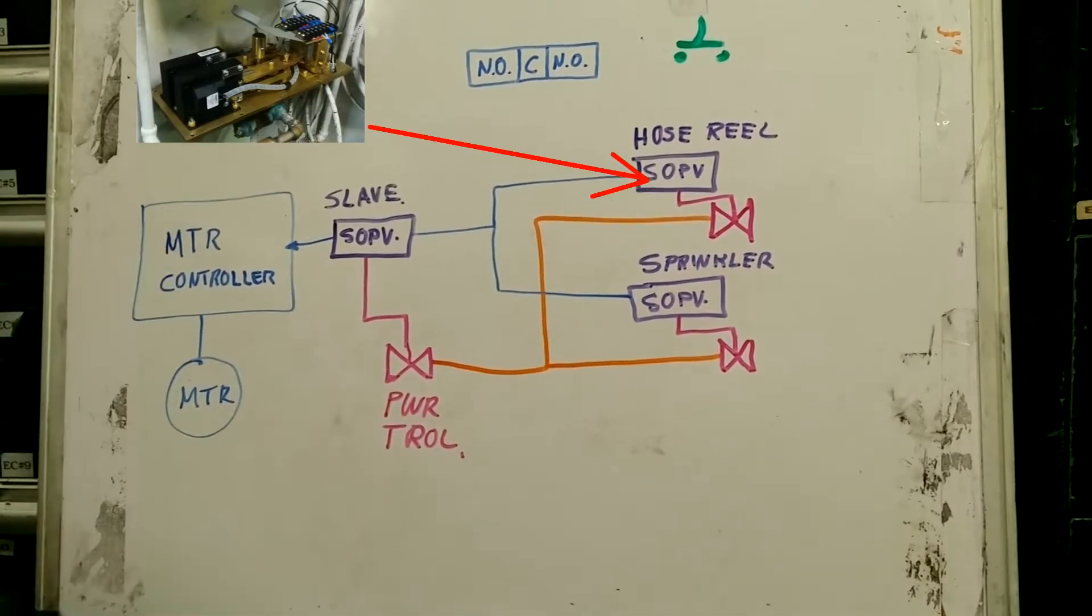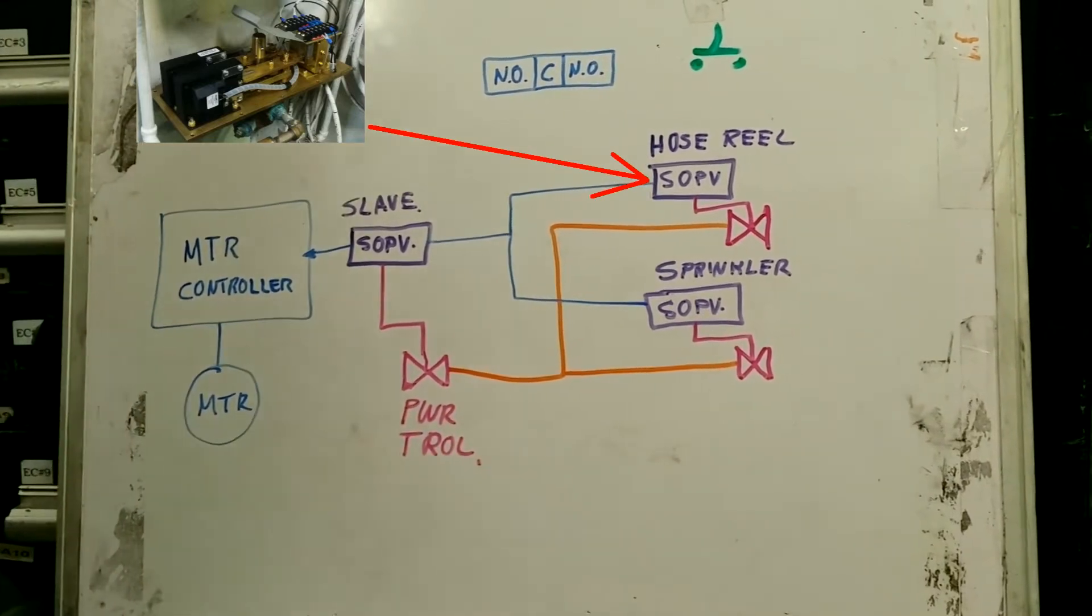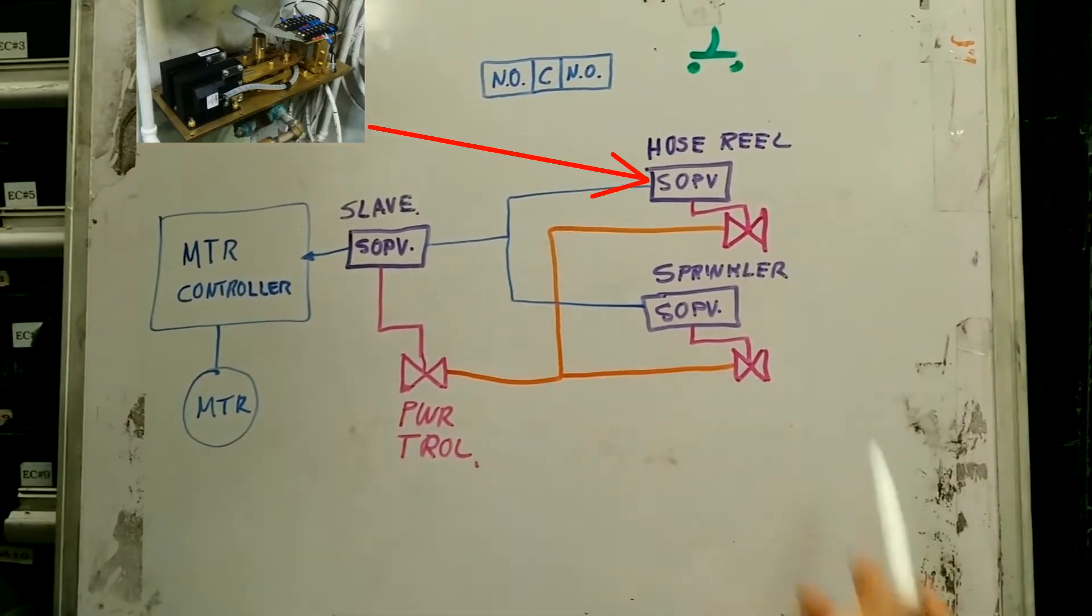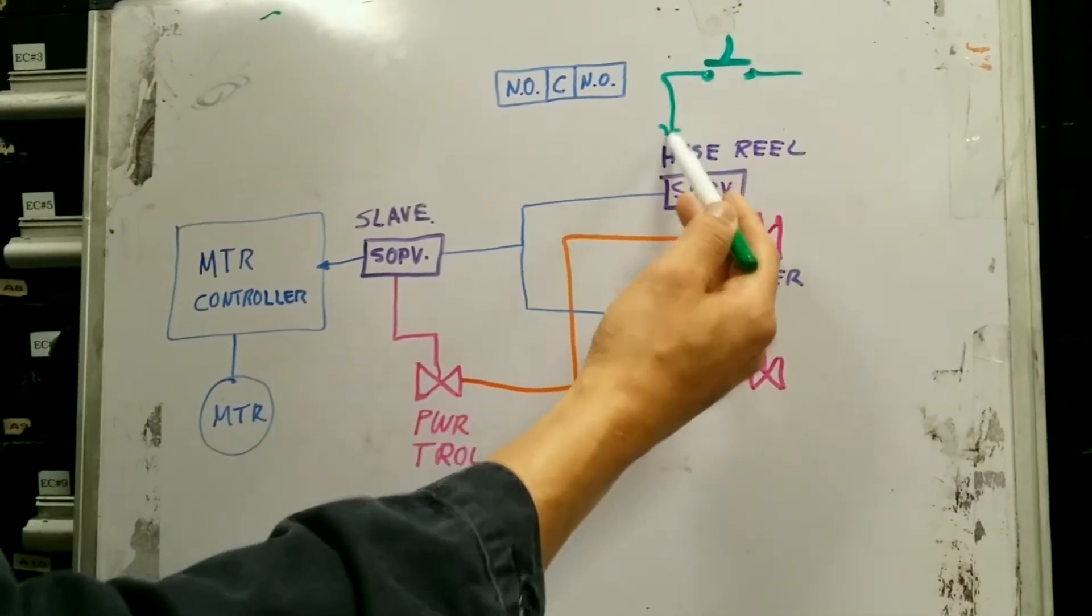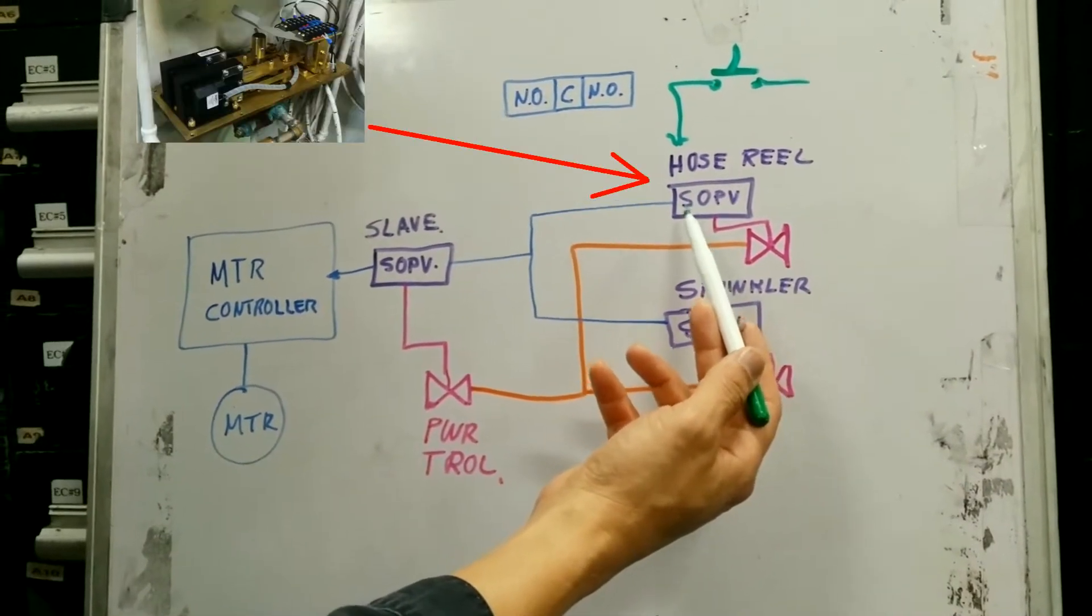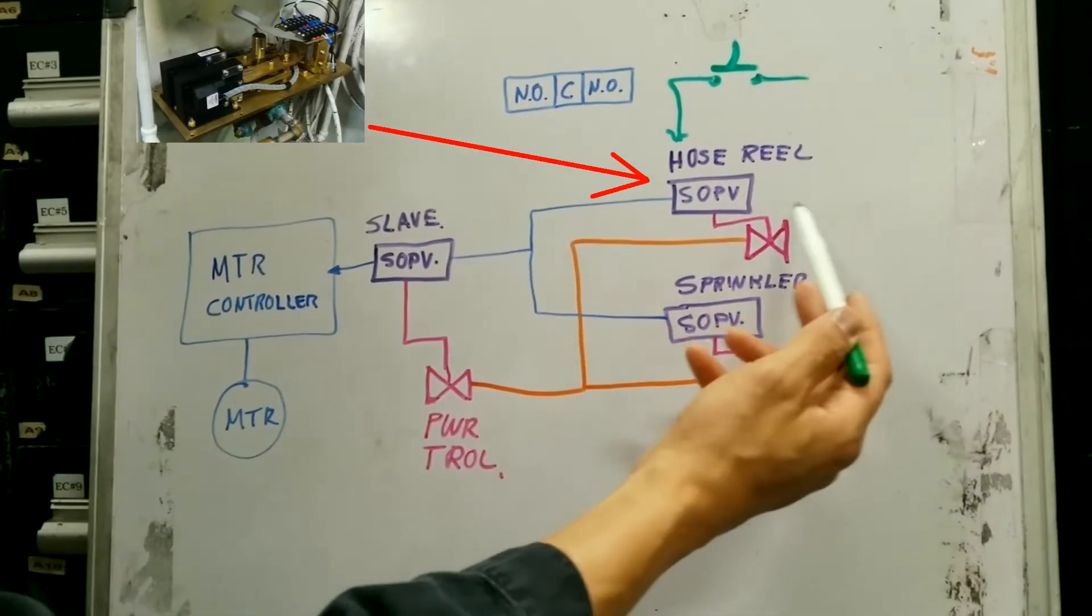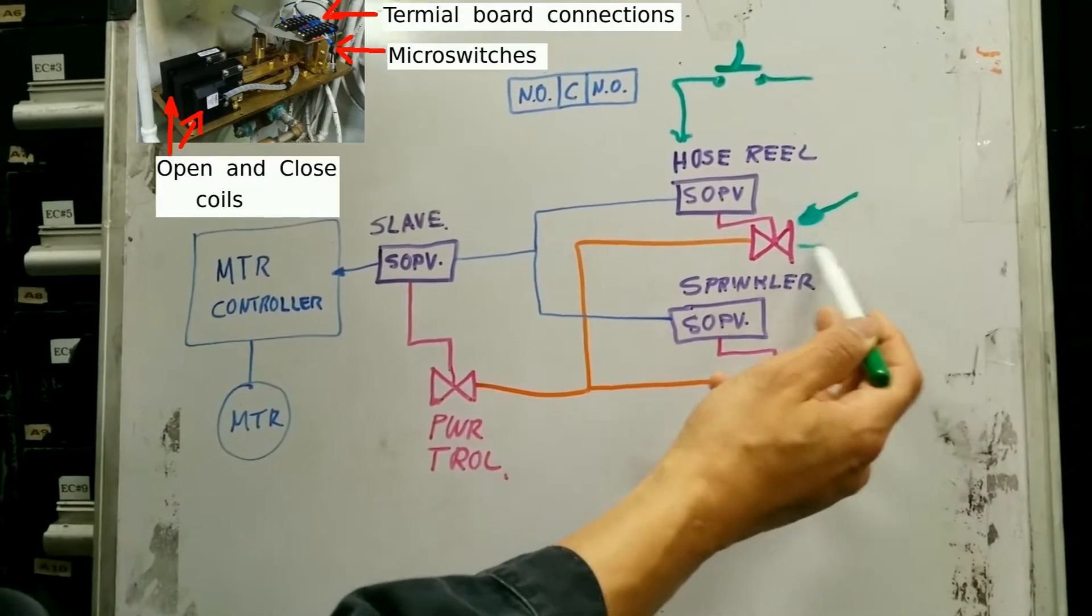The AFFF system is a little bit more complicated than this, but the gist of it is this. So somewhere, let's say there's a fire and somebody wants to press the hose reel button. Whenever they press, they put a signal into the SOPV valve open coil. When the SOPV valve opens, that SOPV opens a local valve for the sprinkler.